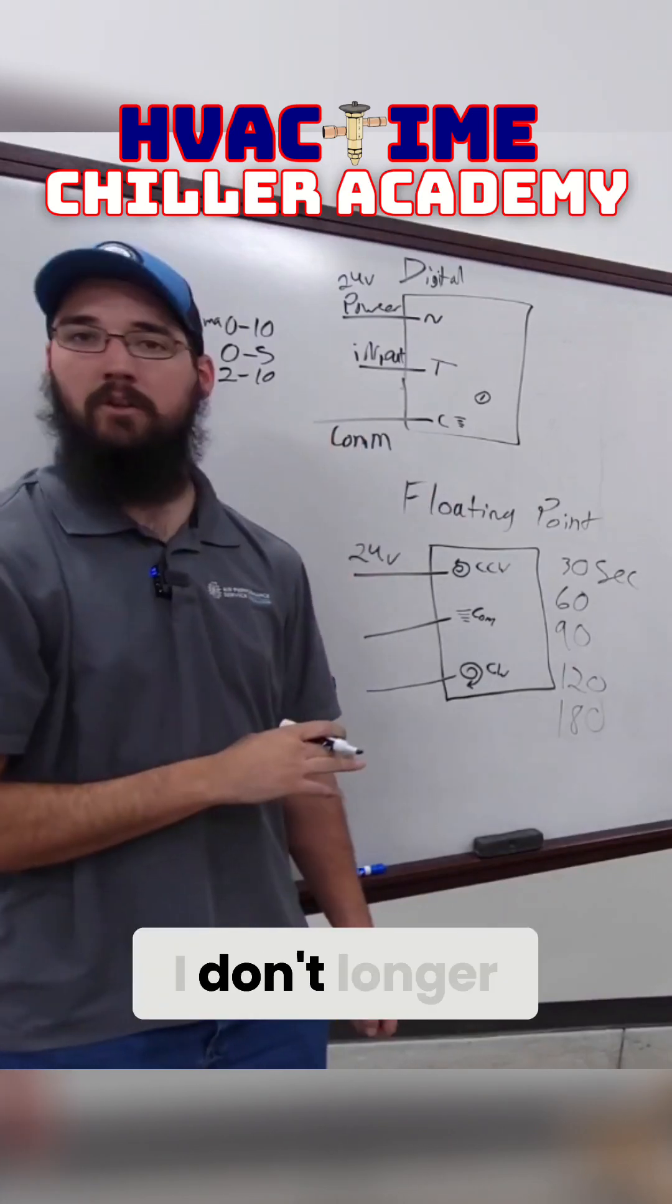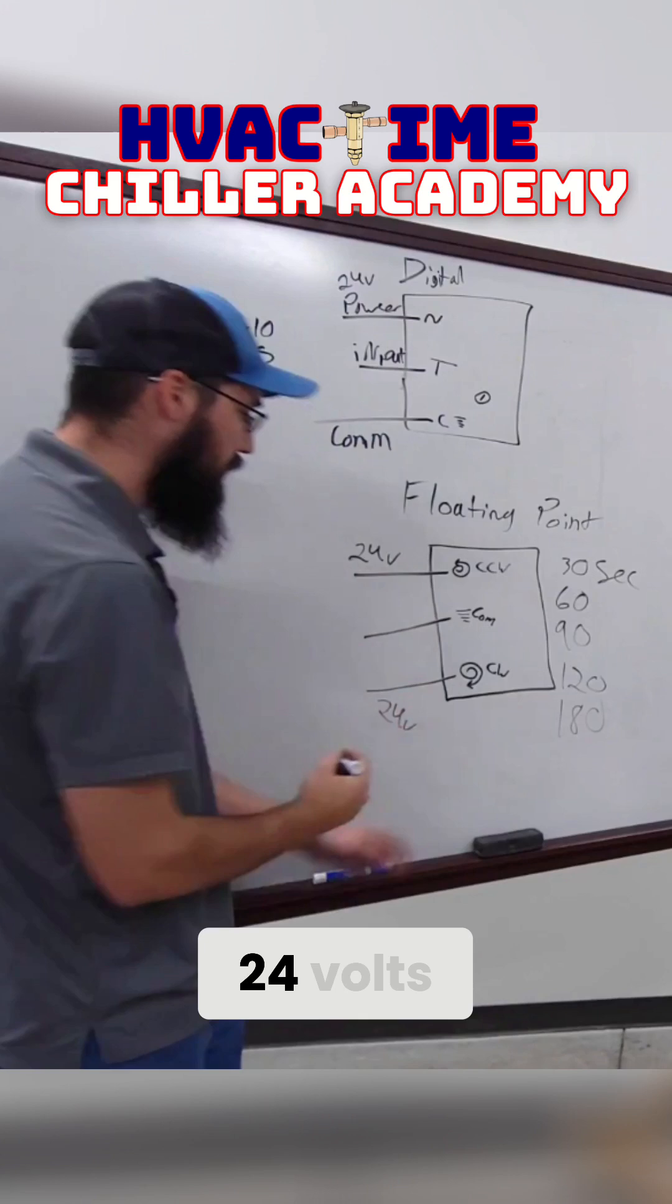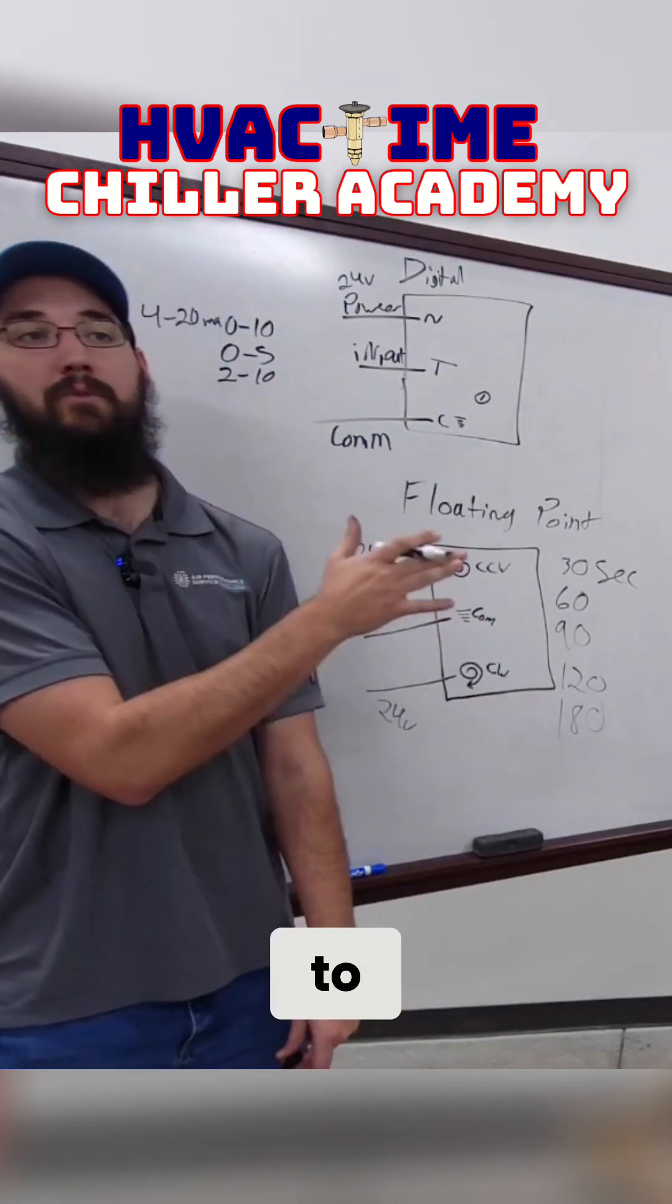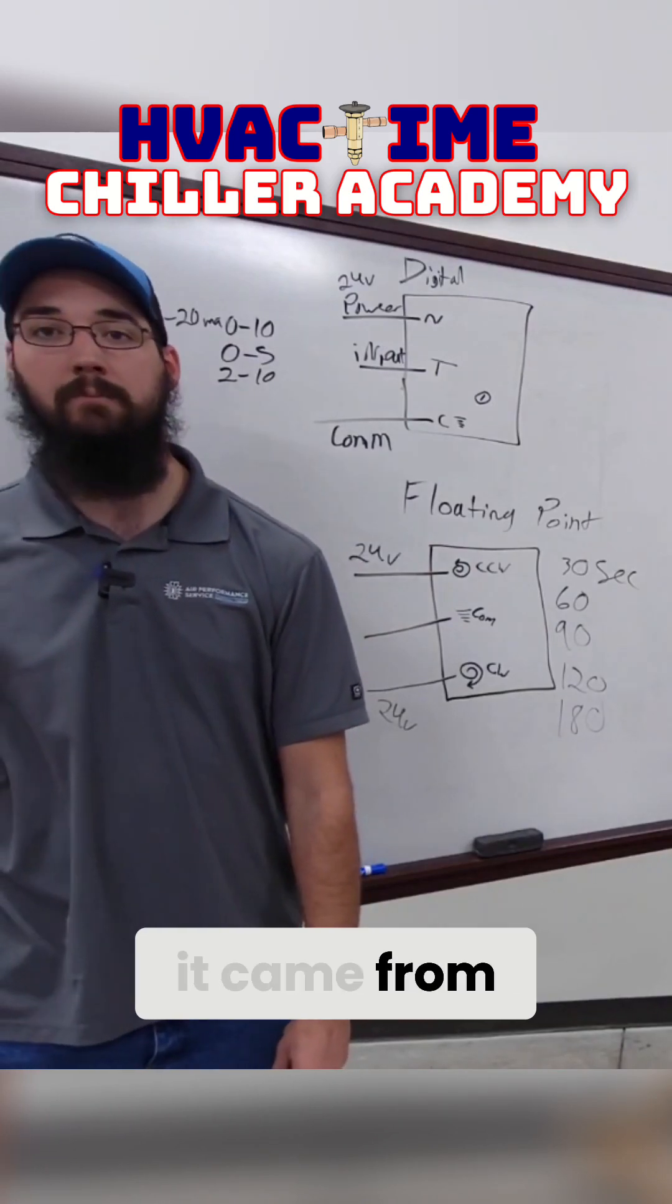And then it decides, okay, I no longer need that actuator open. Then I'm going to feed another 24 volts to the counterclockwise, and I'm going to drive it for 15 seconds and drive it all the way back the way it came from.